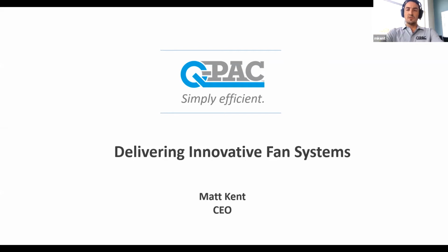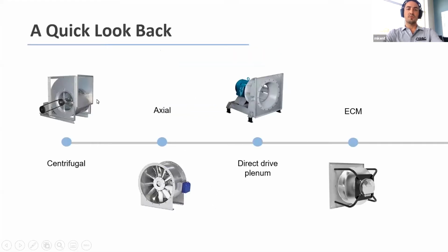A little bit about fan evolution. Many of these probably look really familiar to you all. Starting with constant CFM systems using belt drives and single large fans, then evolving to more direct drive plenum fans paired with variable frequency drives, and moving to arrays of smaller direct drive plenum fans. Now we're starting to see a lot more ECMs, or electrically commutated motors.